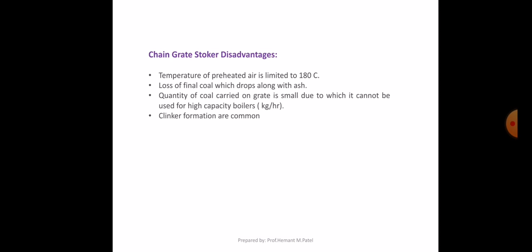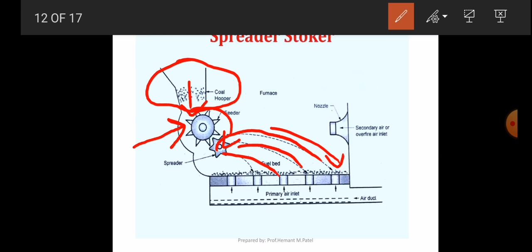Now we are talking about the spreader stoker. The name means sprayed, so the coal is sprayed onto the grate. This is the spreading form. This is the coal hopper, and over here you can see the feeder. Whenever the coal is supplied in this direction, the feeder converts the bigger size coal into smaller size, and after that the coal falls onto the spreader, which sprays it onto the grate area. Air is introduced from the downward to the upward direction, and the coal is fed onto the grate.